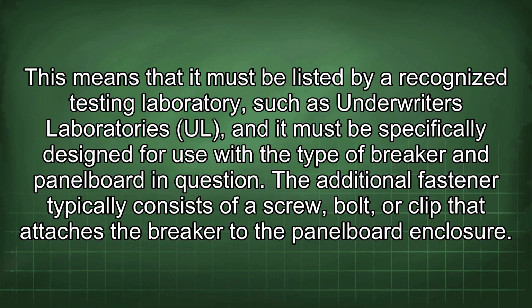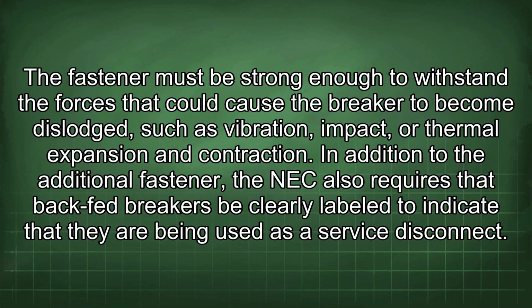The additional fastener typically consists of a screw, bolt, or clip that attaches the breaker to the panel board enclosure. The fastener must be strong enough to withstand the forces that could cause the breaker to become dislodged, such as vibration, impact, or thermal expansion and contraction. In addition to the additional fastener, the NEC also requires that backfed breakers be clearly labeled to indicate that they are being used as a service disconnect.